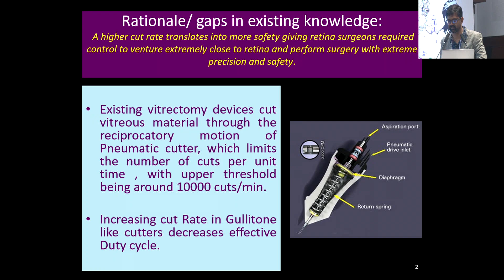The more you increase the cut rate in guillotine cutters, the more the effective duty cycle decreases. So the problem was to increase the cutting rate. There was a lot of hype a few years back when Bausch and Lomb announced its ultrasonic vitrectomy cutters, but it gradually fizzled away. To break that ceiling, we think a rotating tool, instead of a reciprocating tool, has the possibility to break that barrier, and you achieve safer and faster removal. With a rotating cutter, you can do multiple cuttings because of this rotary action rather than a reciprocating cutter.